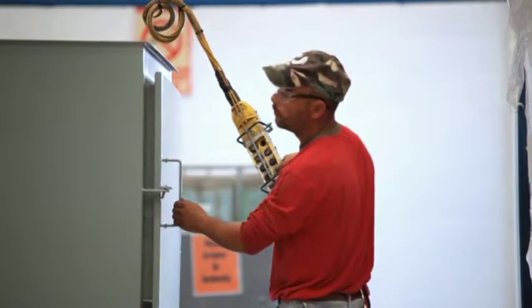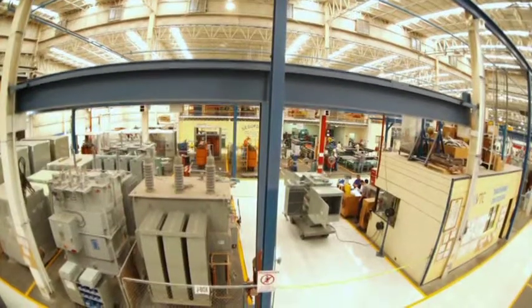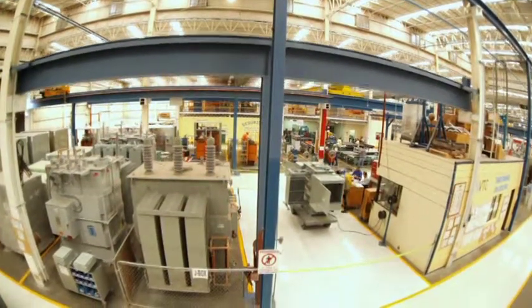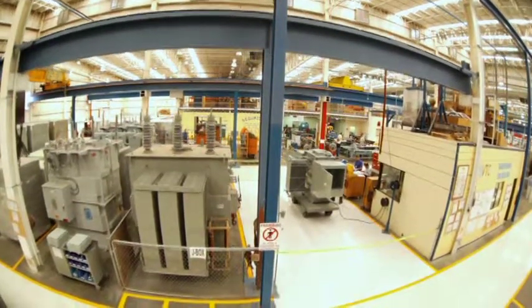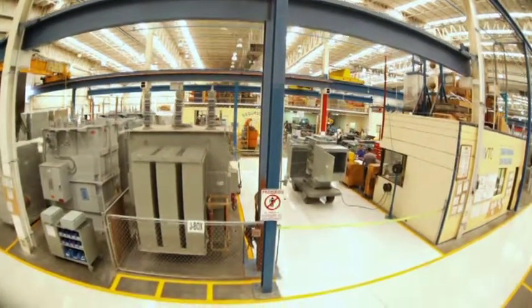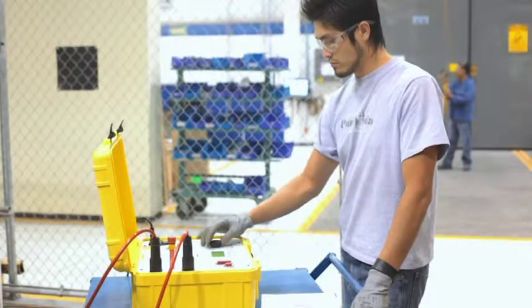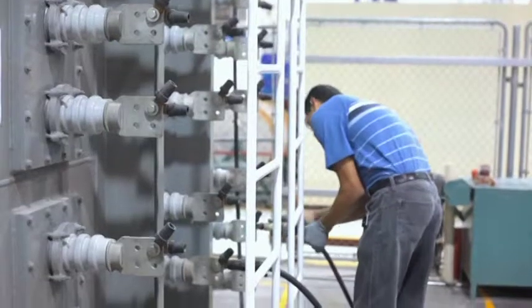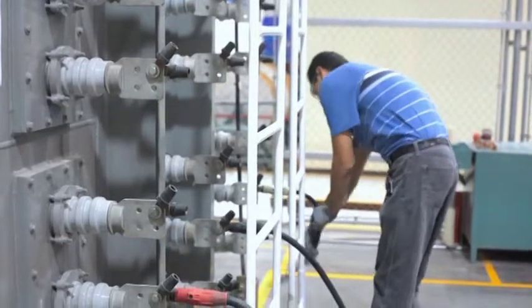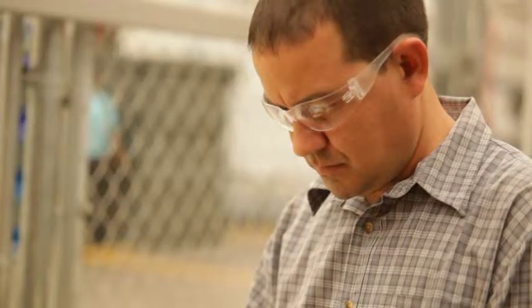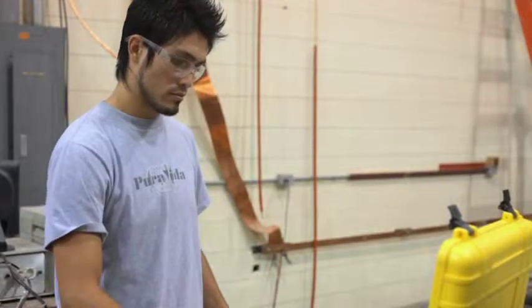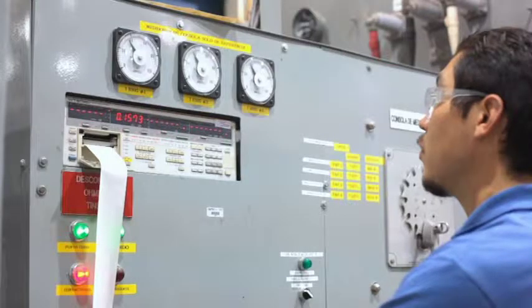Once the unit has been assembled entirely, it goes to our electrical testing laboratory, where it is verified at 100% using modern, updated test equipment that is required to carry out routine testing, validation, and special testing on power transformers. All tests performed in our laboratory meet strict U.S. standards, ANSI, IEEE, CSA, and ISO standards. Our test engineers have been trained to implement all the required electrical tests, as well as to make appropriate interpretation to ensure a safe and effective operation of the transformer.